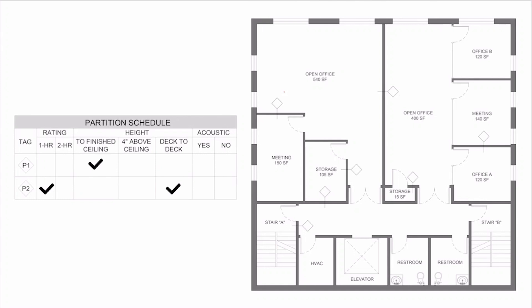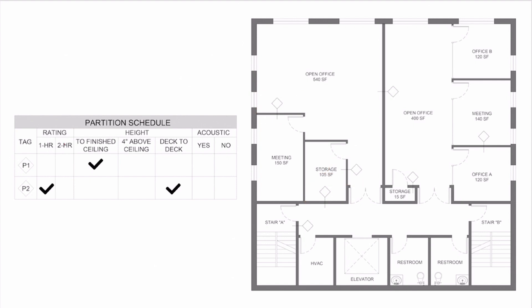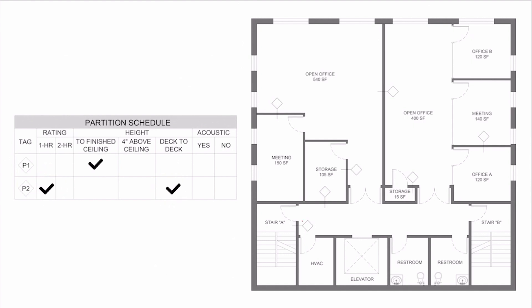On the plan, we have partition tags — the diamonds with the line. Those diamonds are tagging that wall to tell a contractor how to build it or describe the properties of that wall. From the partition schedule, P1 is a non-rated wall — it is not fire rated, does not have a rating check mark, and it goes up to the finished ceiling. We know fire rated partitions go deck to deck, so this confirms that. P2 is our one hour rated partition — it's checked one hour and goes deck to deck.